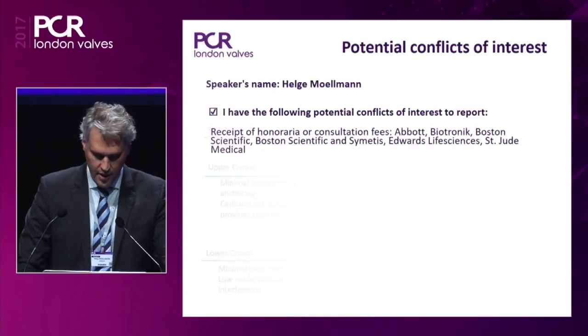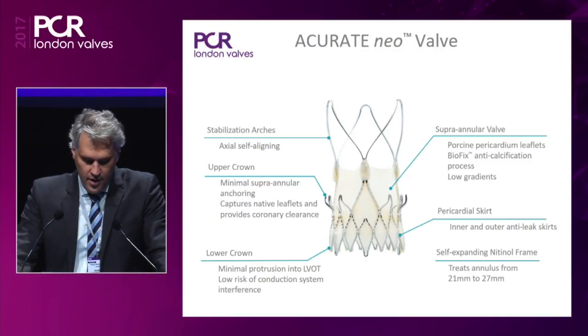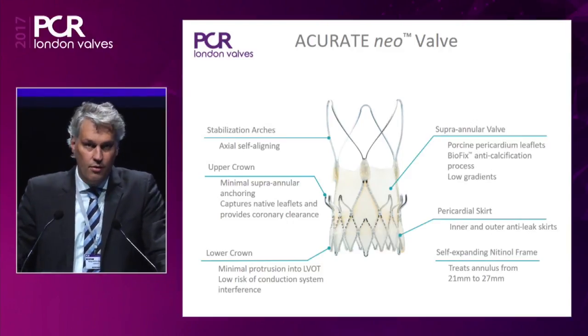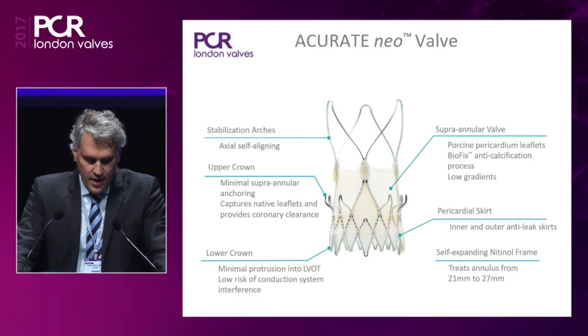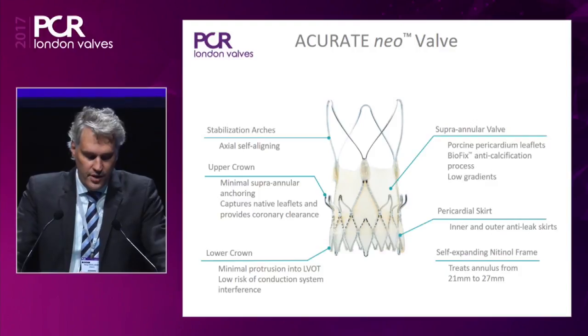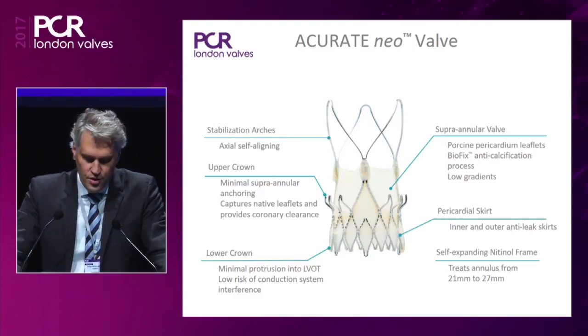When we are talking about the ACURATE device, we are talking about this valve. It's a self-expanding valve made out of nitinol. We have stabilization arches at the upper part of the valve which help to self-align the valve during deployment — a feature which is very important only during deployment; afterwards it's not meant for anchoring. We have the upper crown, which helps to capture the native leaflets and to provide coronary clearance. We have the lower crown with minimal protrusion in the LVOT in order to minimize the risk of conduction system interference.